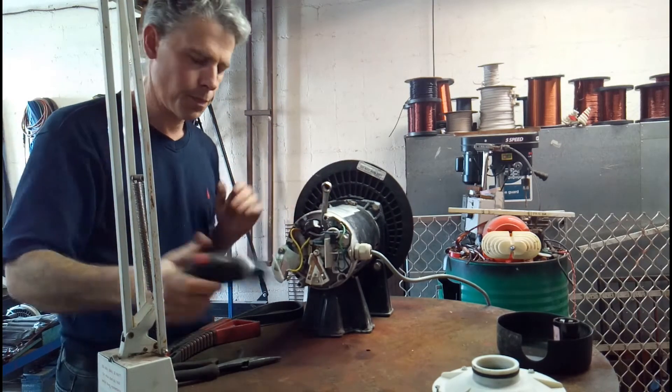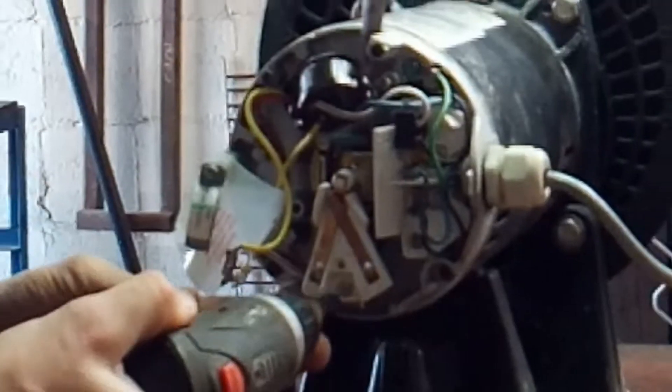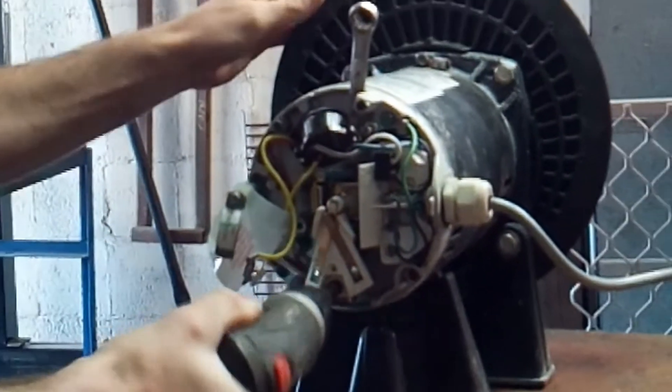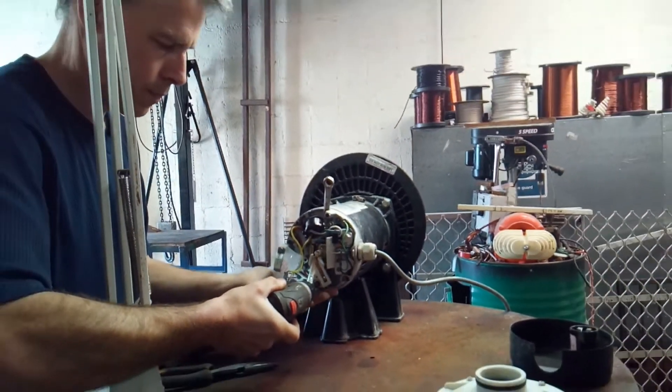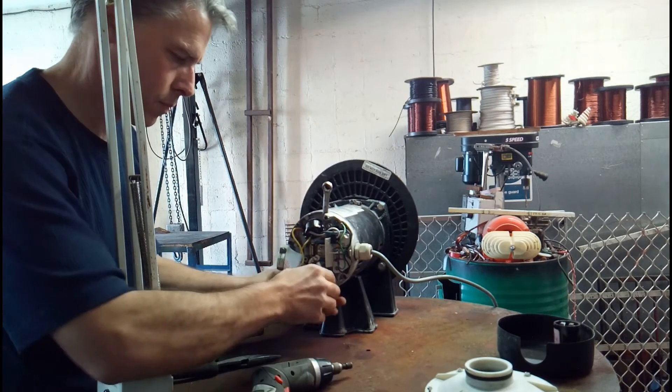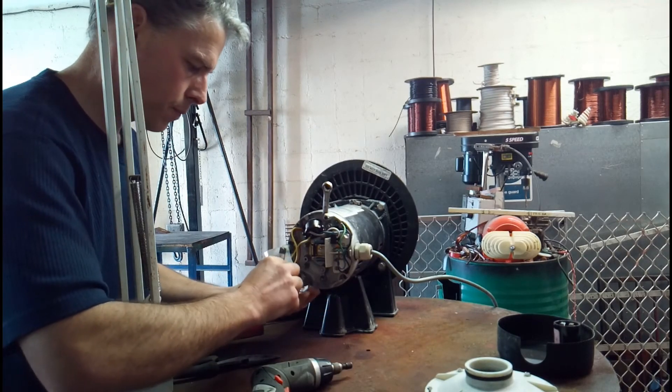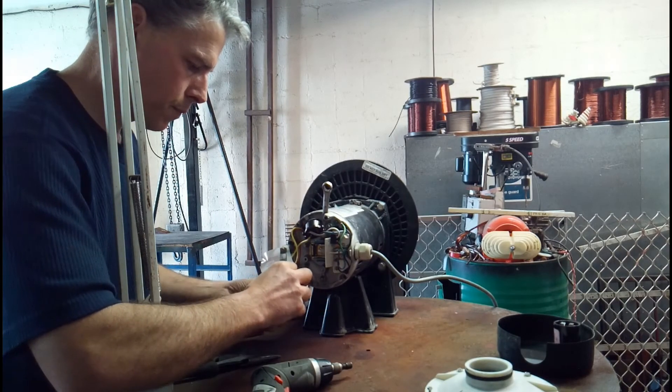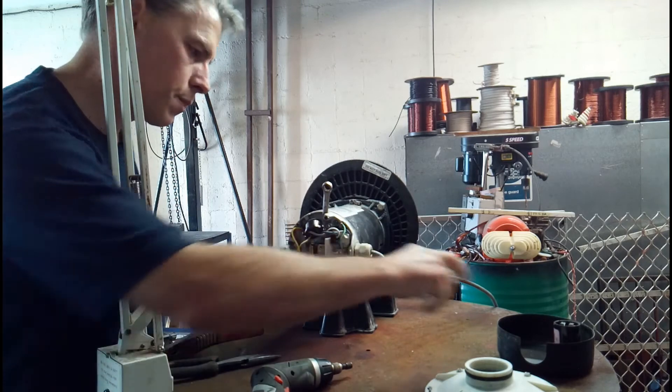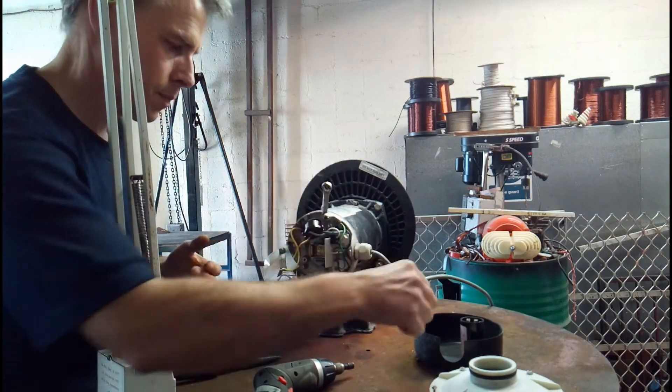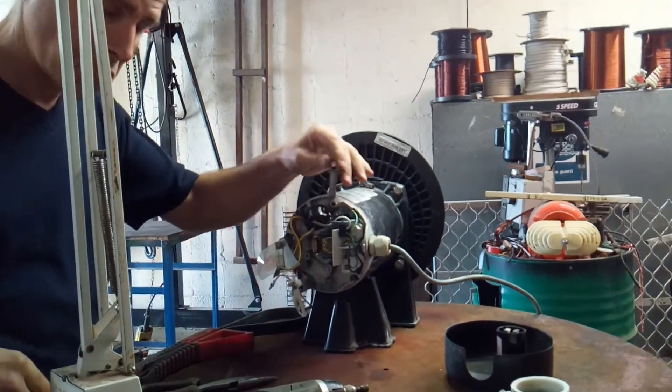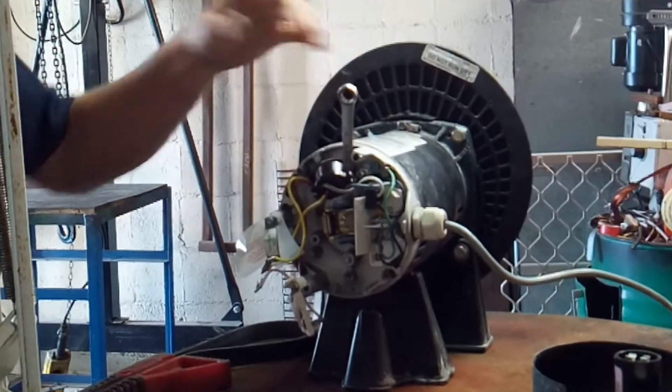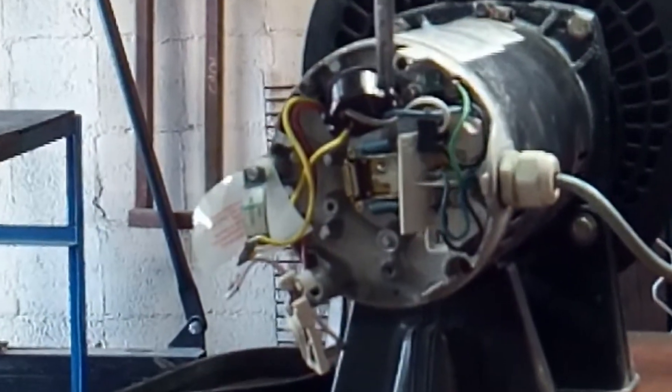This is the part where we remove the contact part of the centrifugal switch mechanism. This is the switch that opens the circuit and takes out the start winding once the pump is up to speed. Just put them in there to keep them safe. And now we're ready to take off the seal plate.